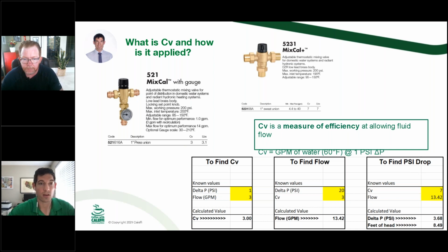So in the Caleffi catalog, we've got the MixCal, and then we've got the MixCal Plus, which is a much bigger valve body. But look at the different CVs. The valve on the left is a 3 CV, and the valve on the right is up to a 7. So same 1-inch connections, but completely different size bodies there. So to go back a little bit, CV is a measure of efficiency at allowing fluid flow. For the example on the left, to find CV, we've got a delta P of 1 PSI, 60-degree water, with 3 GPM. That matches that 521 on the left at 3 CV. It's going to lose 1 PSI as you flow 3 GPM across.